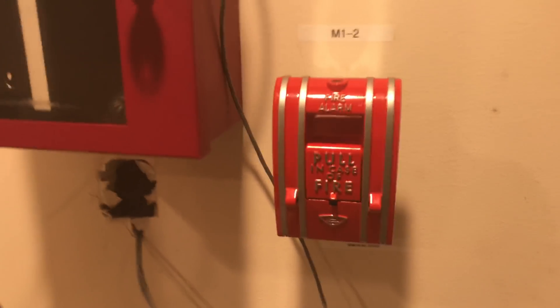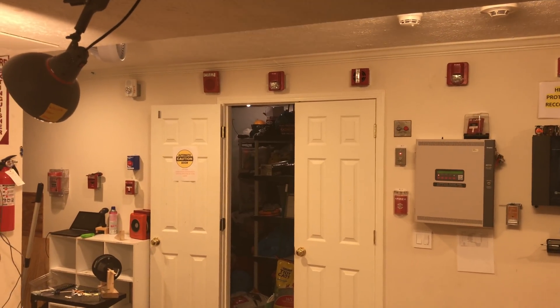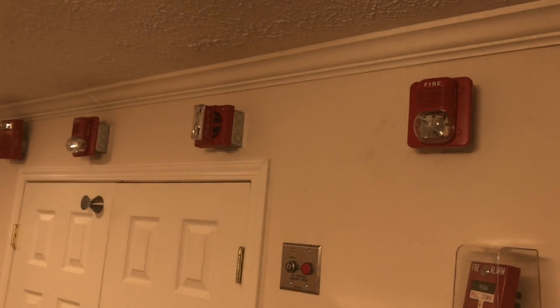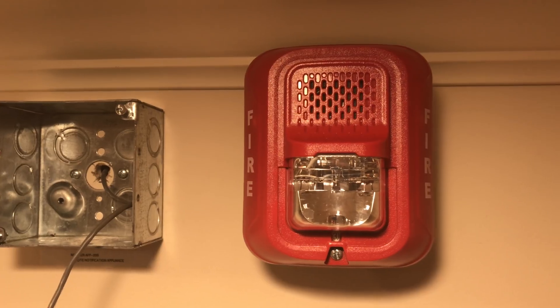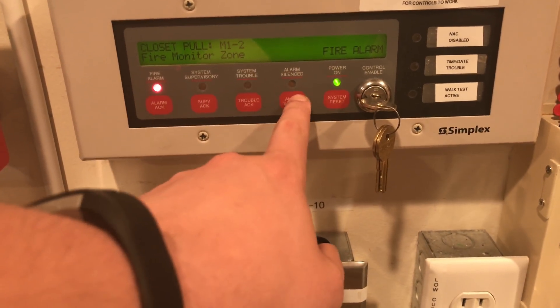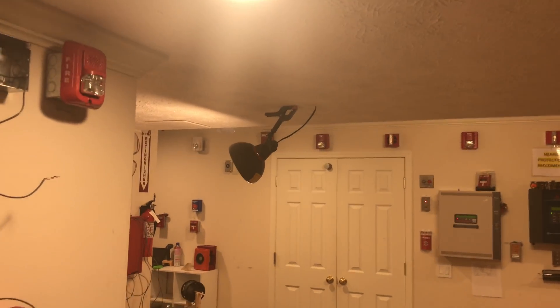To begin I think we will just start with the pull station. Here we go and pull. It will go ahead and sound from the annunciator. These are all on two-wire audible silence so all the strobes are in sync and they all silence on two wires.